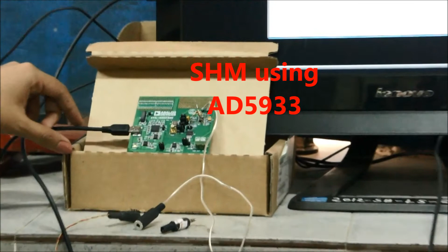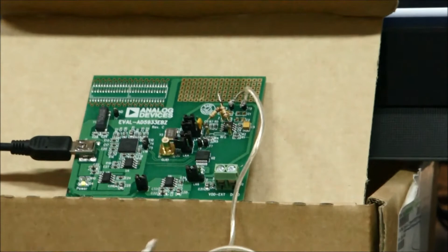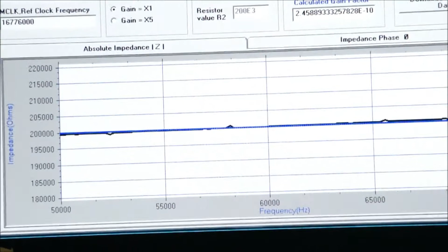Next is an AD5933 circuit, which is an alternative circuit for an LCR meter. For starting this circuit, it has to be first calibrated with a 200 kilo ohm resistor. So we'll connect this resistor with the circuit and we'll give a start frequency of 50 kilohertz and a delta frequency of 200 hertz. Number of increments are okay, and we'll give internal oscillator, then start the program, device registers okay, calculate gain factor okay, then measure the temperature, enable the theoretical calibration profile and start sweep.